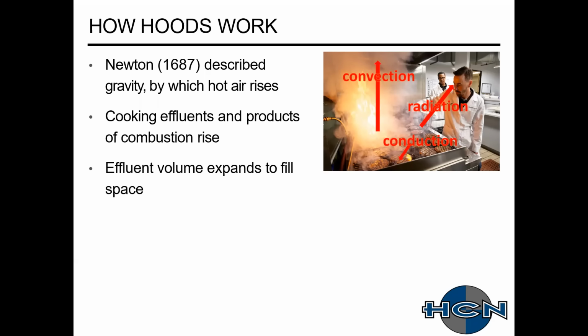So how do hoods work? Heat rises. Typically when you're cooking, you're releasing convective heat, and smoke, effluent, grease particles, that kind of stuff is going up into the hood. And then we're also trying to exhaust as much radiant heat as we possibly can. You're not going to get all the radiant heat, so there is some radiant heat gain.